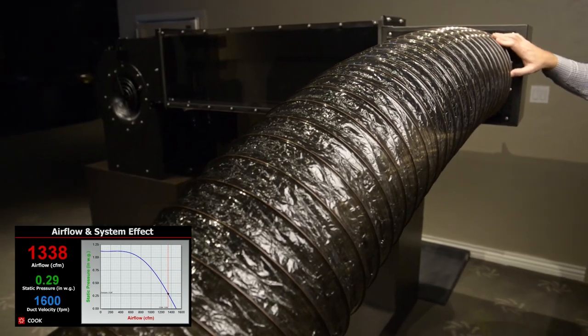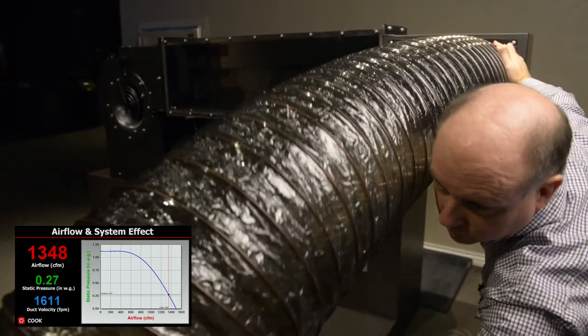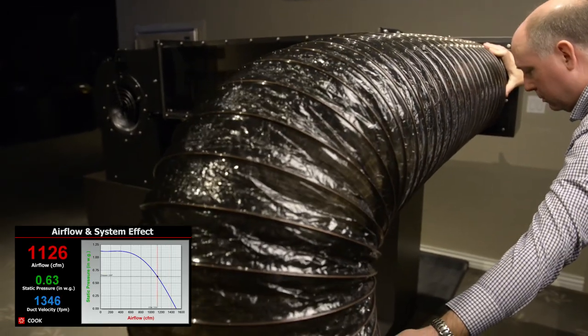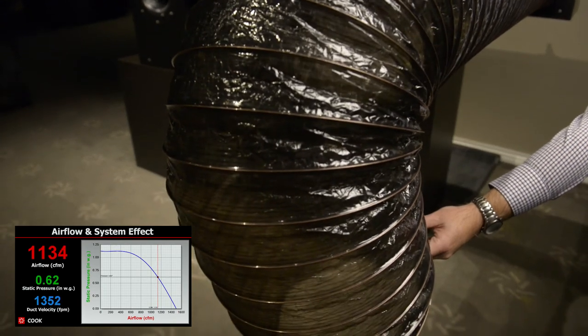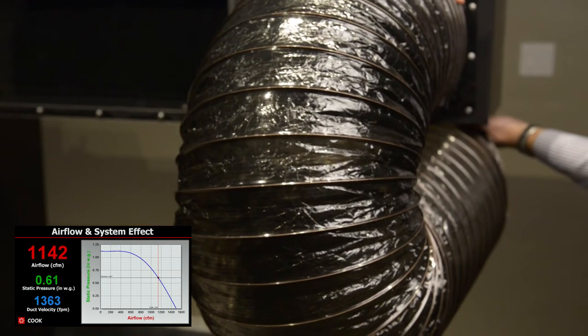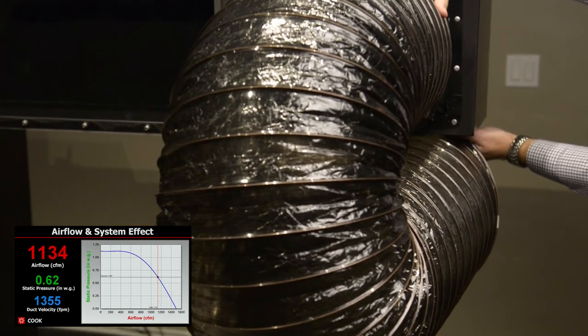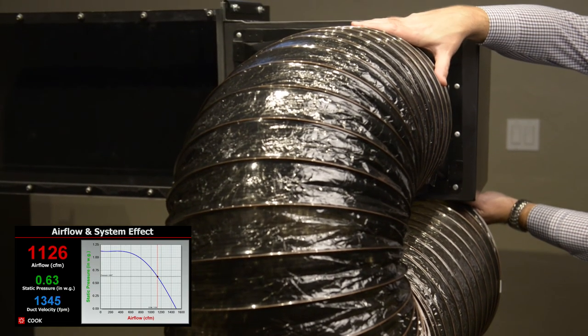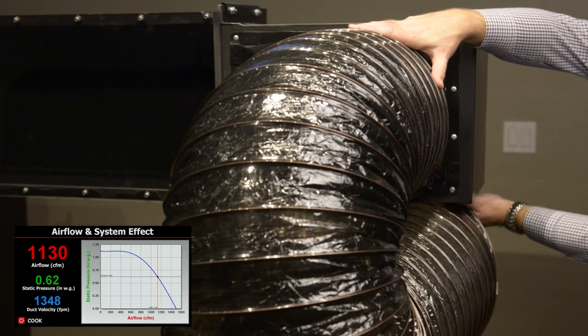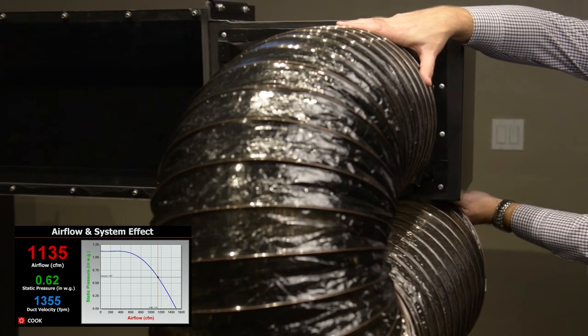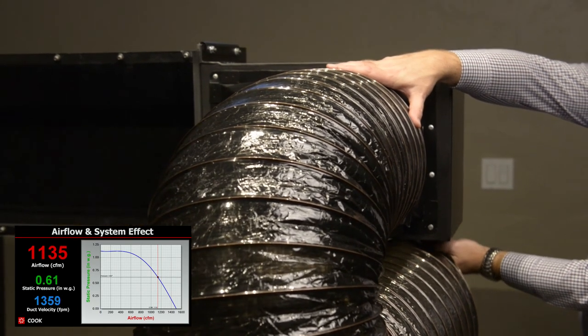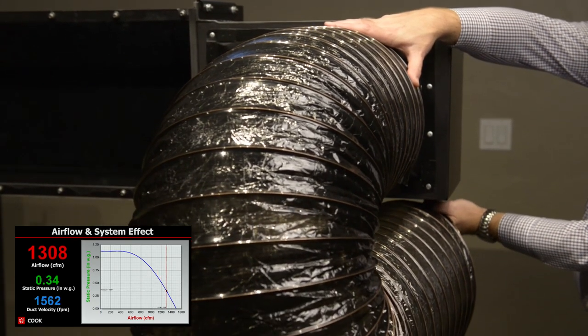Flex duct is generally used to make it easy to connect to a diffuser. In the most severe case, this could mean a 180-degree bend. As you can see, the pressure loss may increase dramatically. Here we see a surprising 0.6. This demonstrates the importance of properly applying flex duct, keeping lengths as short as possible, velocities low, and bends gradual.